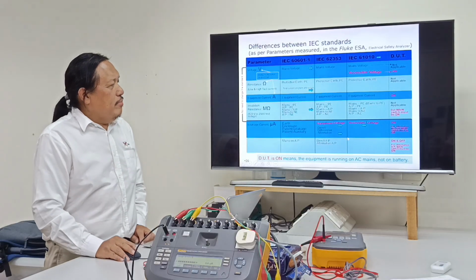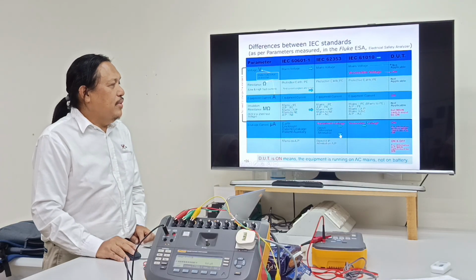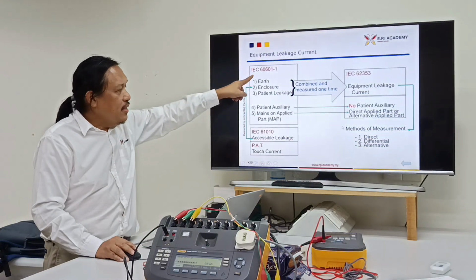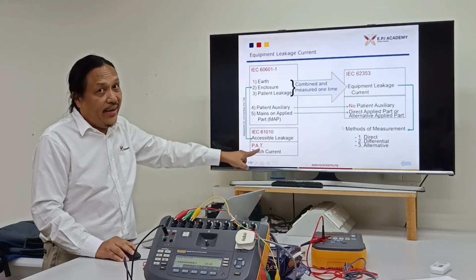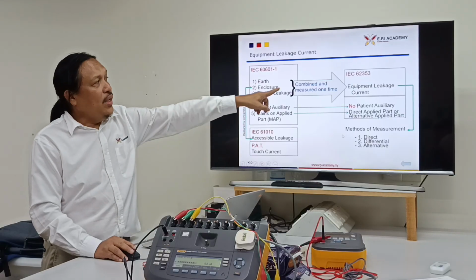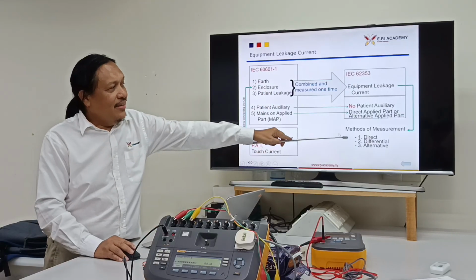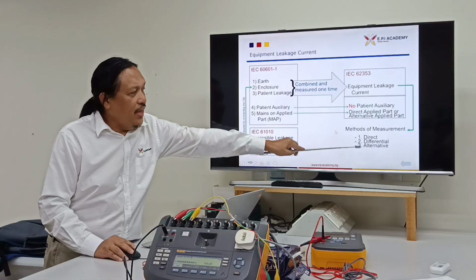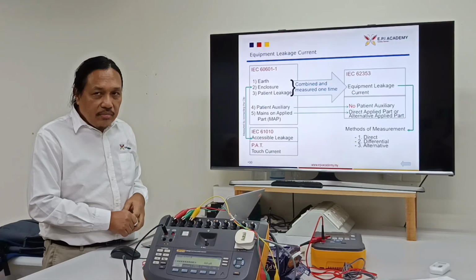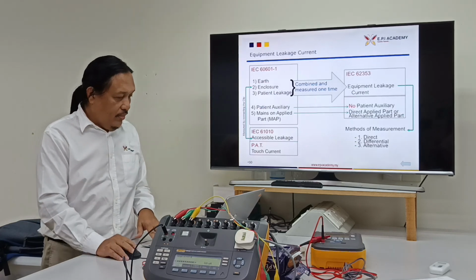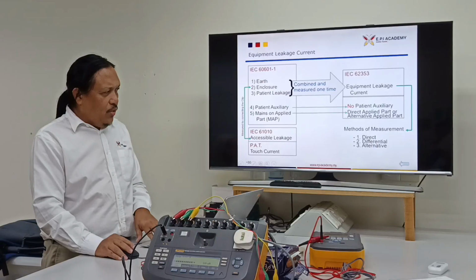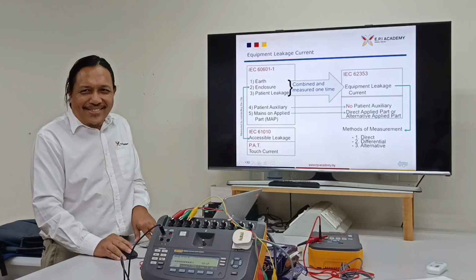Why direct method? This is direct method. By the way, all of these standards are all direct method of measurement. Only 62353 has one more, differential and alternative. So I think that direct method is no need to explain.